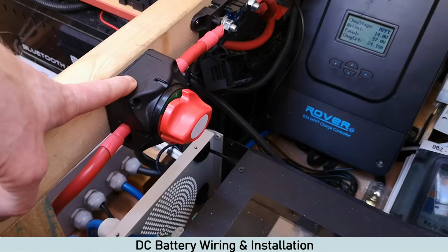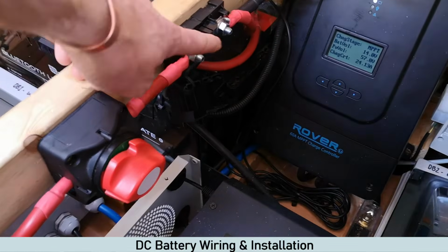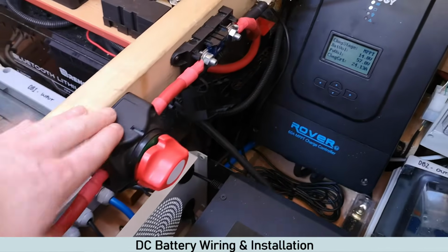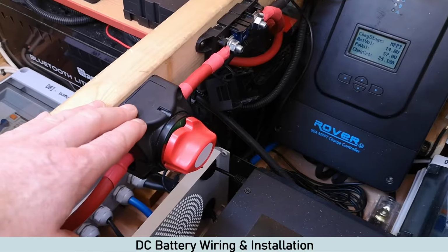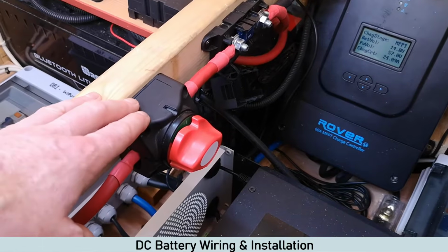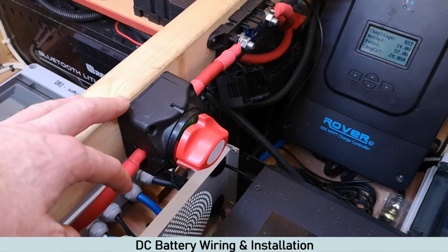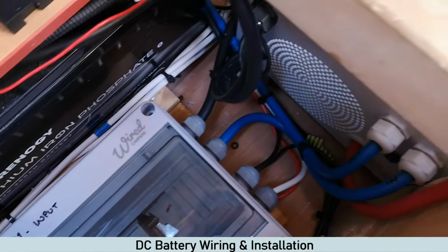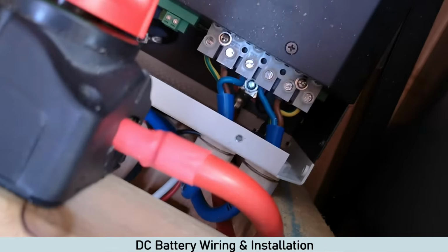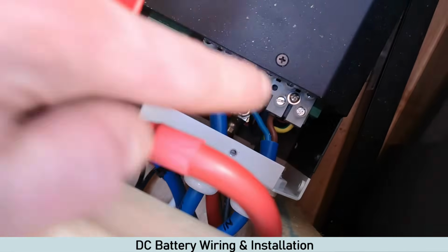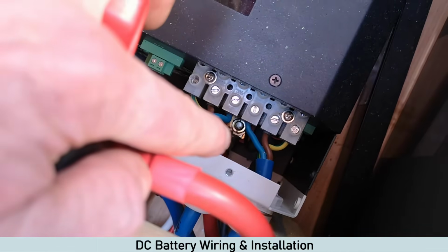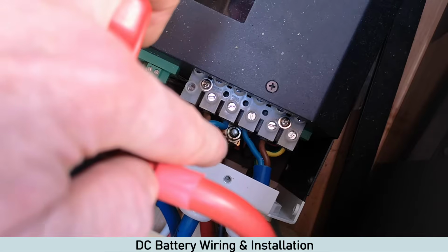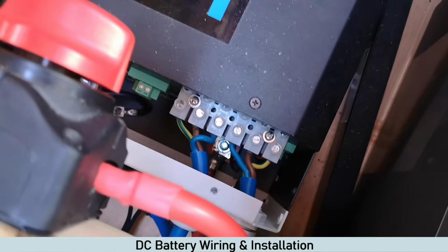Ours is rated at 300 amps. We've got a 200 amp fuse, so we need this to be higher than the fuse basically, so it can carry the current. So we've just gone for a 300 amp. So from there it goes down here into the inverter charger, and you can just see the terminal right in the middle there. There it is. So it's right down there. That's our positive terminal for the inverter charger.